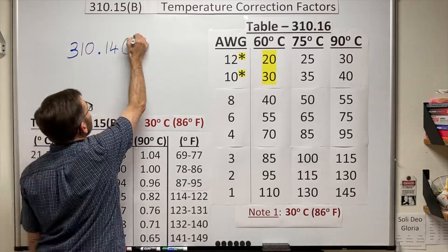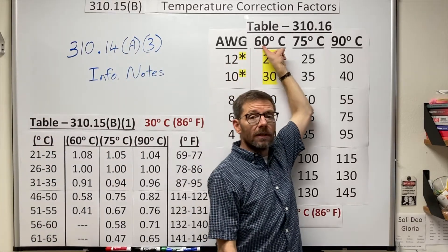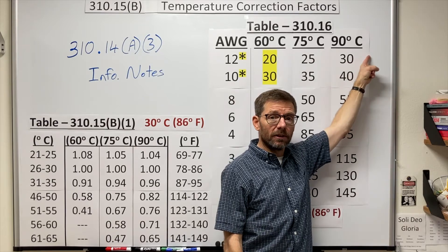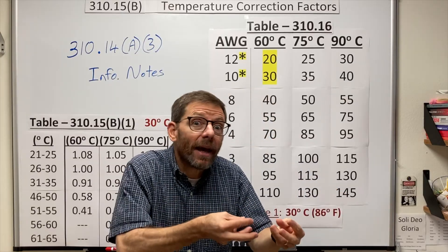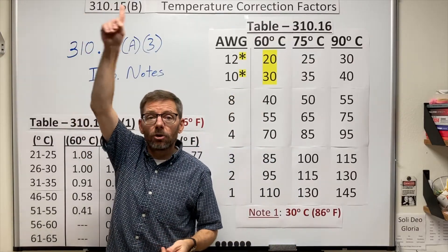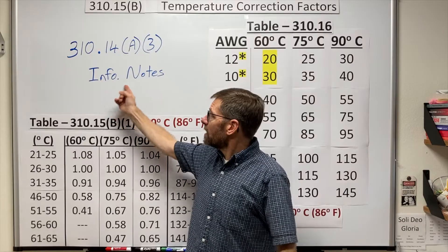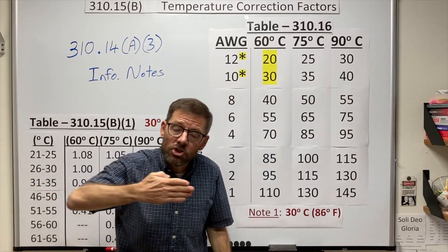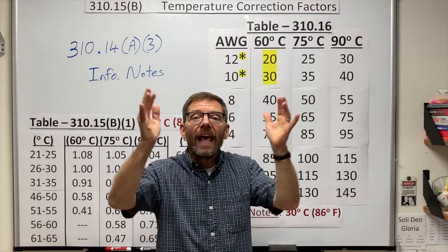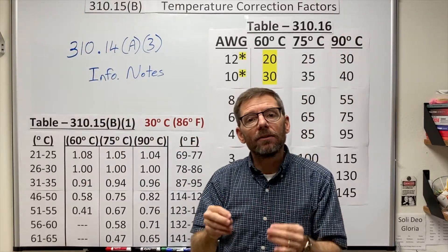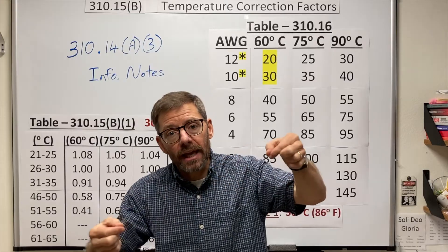Let's start this video by looking at the informational notes below .14A3. What we find here is that the temperature rating of a conductor cannot be exceeded for prolonged periods of time — otherwise we risk damaging or degrading the insulation. Also, as a conductor works its way through a building, it may encounter different ambient temperatures in different locations. These notes go on to say that the heat generated in any conductor simply by virtue of it carrying current must be dissipated into the ambient medium — meaning the air, the insulation, the concrete, whatever directly surrounds your cable or conduit.